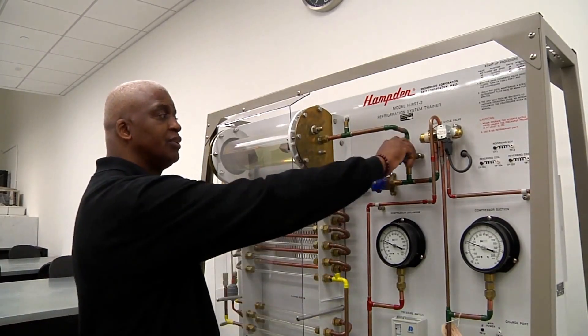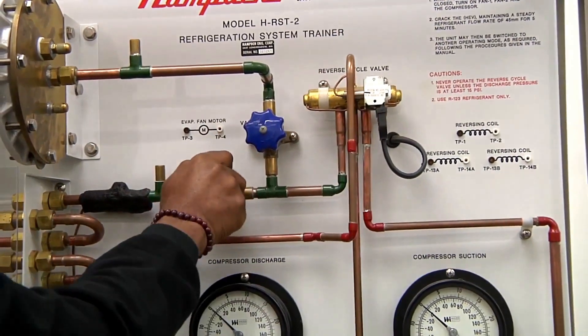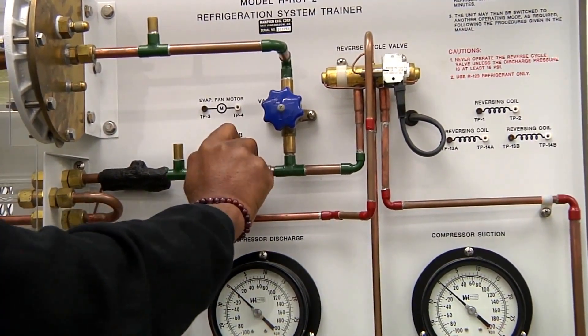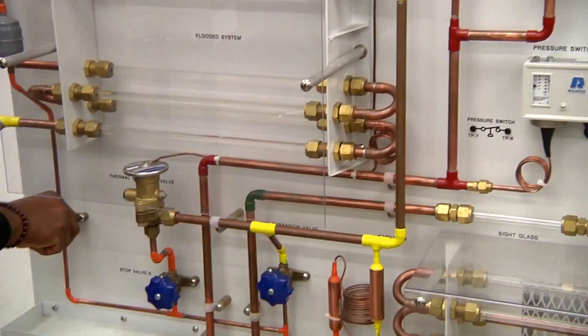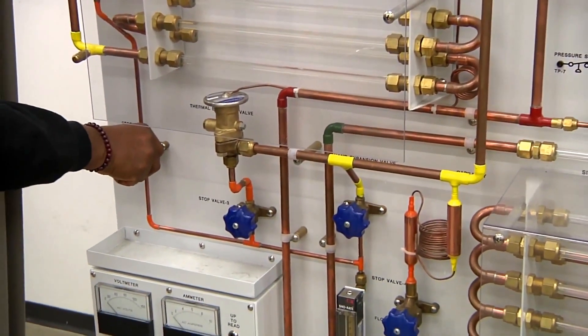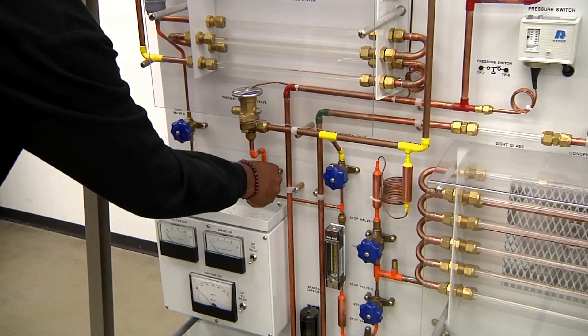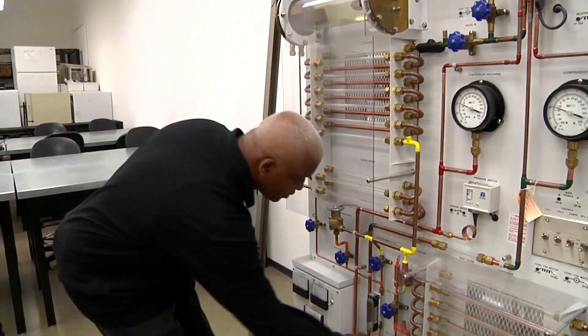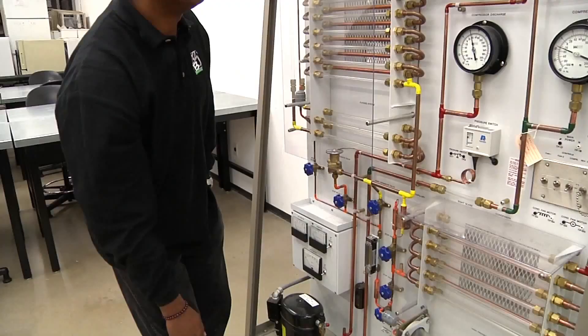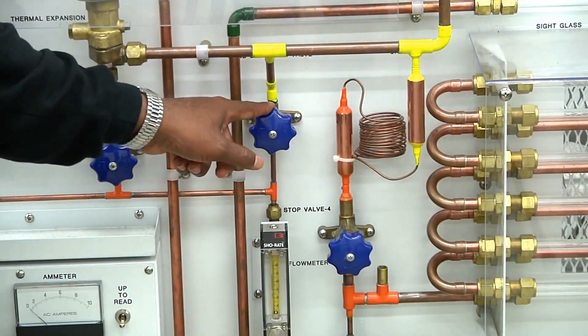A1 has to be closed — that's a valve. We make sure this valve is closed. B1 is open, so we make sure this valve is in the open position. We come to valve number two and make sure it is in the closed position. Valve number three is also in the closed position. Valve number four is also in the closed position. Valve number five is in the open position, and valve number six is in the open position. Now our Hampden Trainer is ready for operation using our hand operated expansion device.